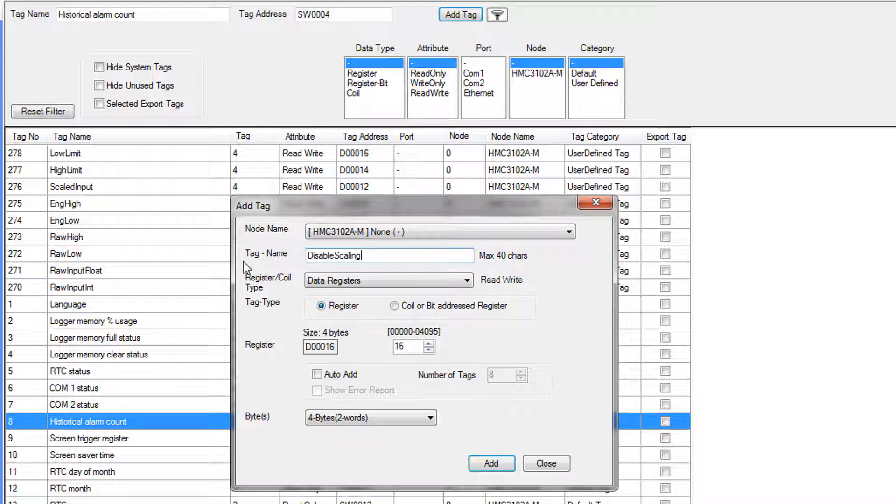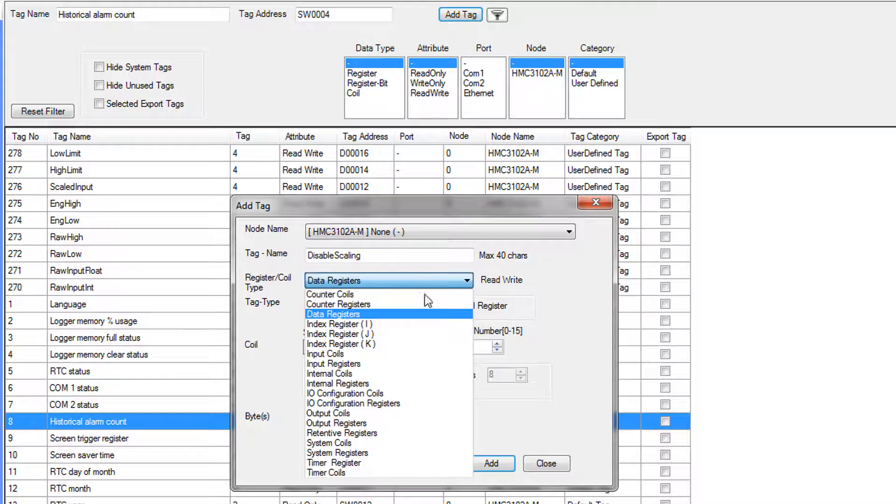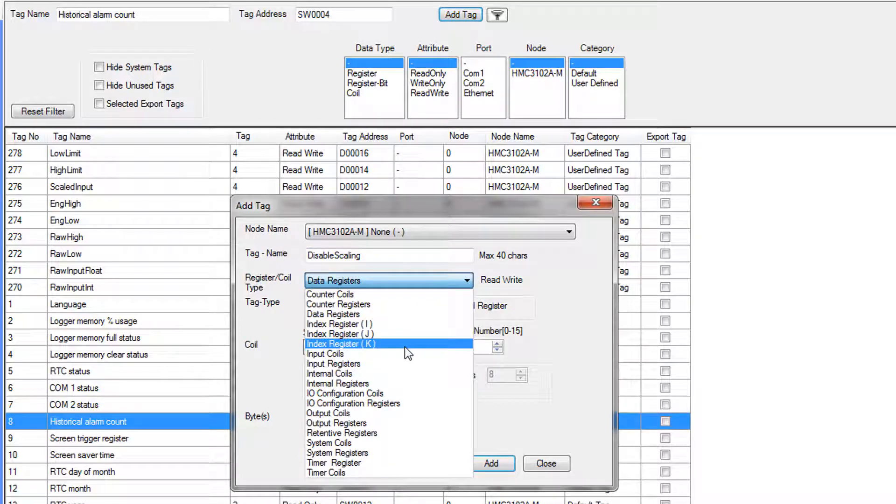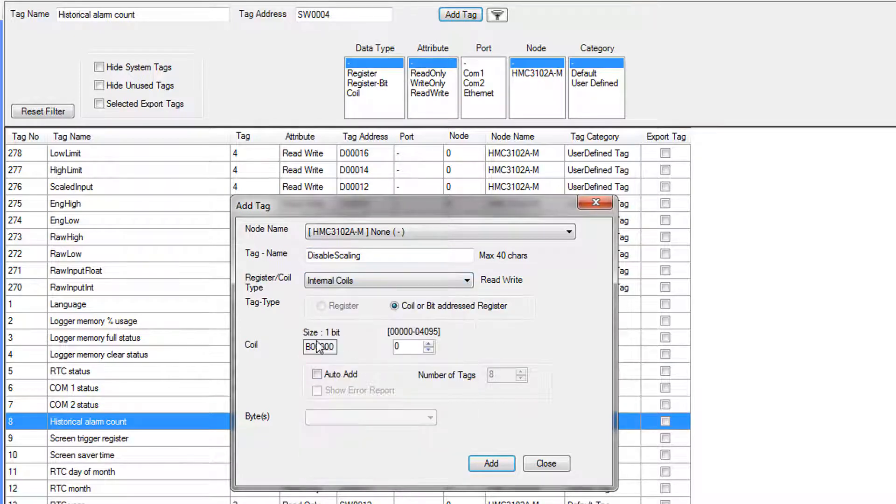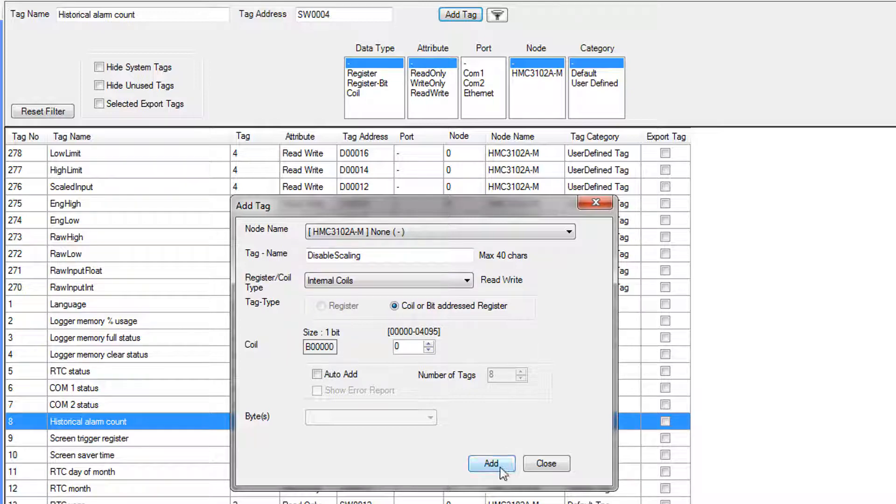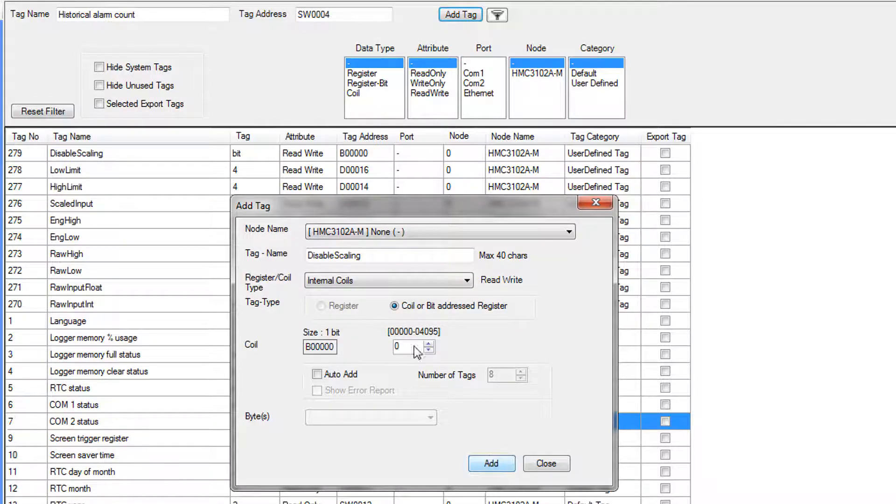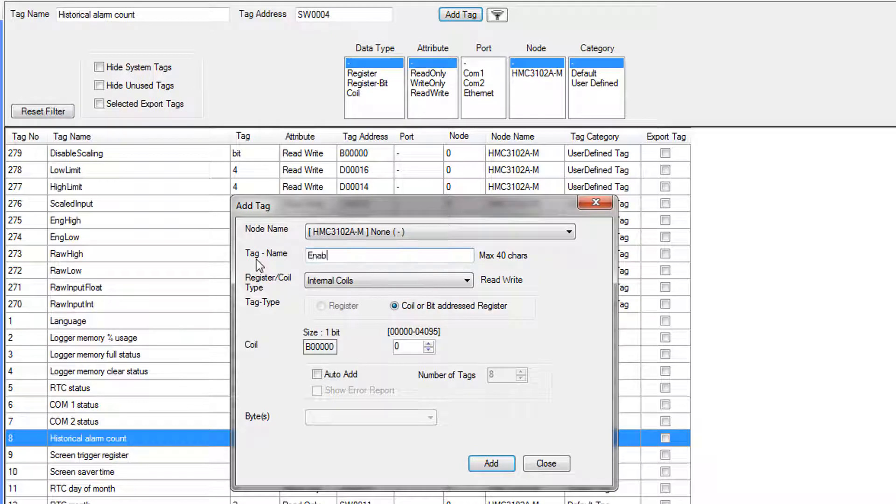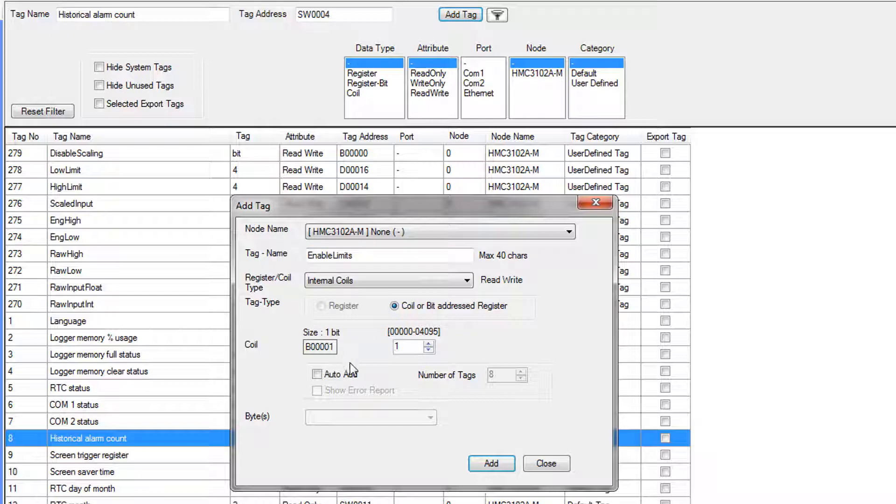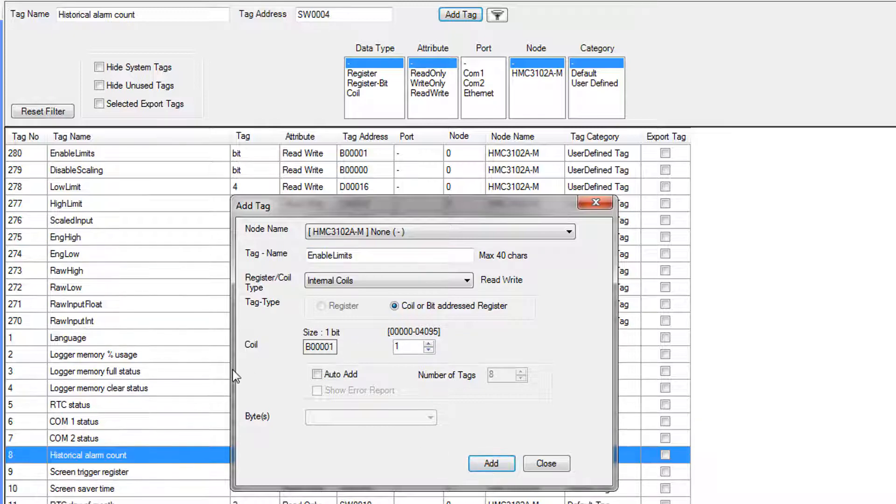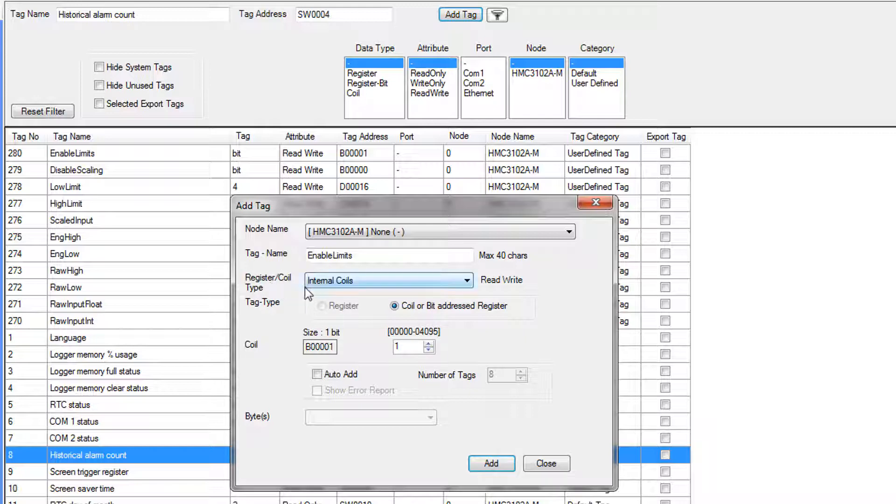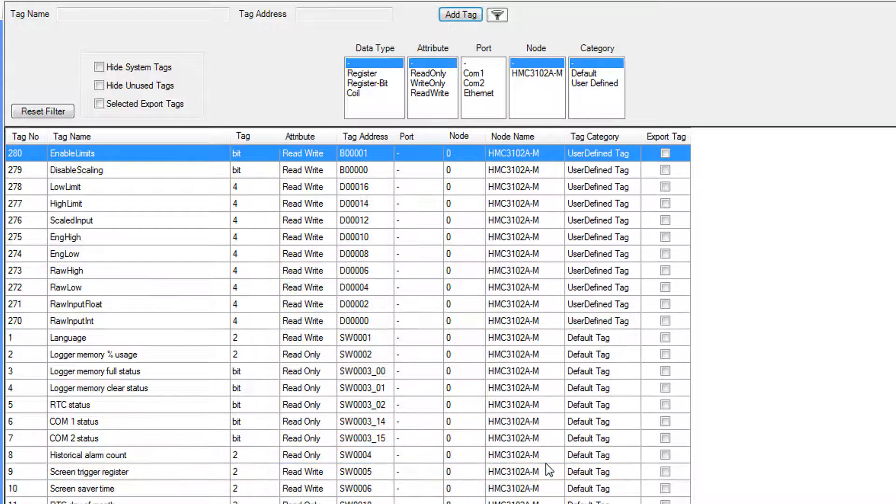Once we get to disable scaling, this is actually going to be a bit address, and we're going to put it in the internal coils. That's going to give it a B address, and so this one will be assigned to B0, and enable limits will have address B1. These are all the initial tags that we're going to add. We will be creating some more tags later within the logic, but these are the starting tags. We're going to hit close.